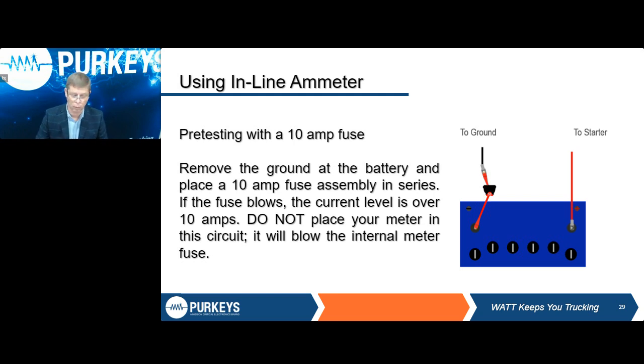What you want to do is, we always recommend doing the ground side. It's just safer, less likely to have sparks. So you're going to have to round up all your grounds that are connected to those batteries and bolt them together so you have one common junction point. Put that fuse holder in line. If it doesn't blow, it says, hey, you're under 10 amps, you should be fine to put your meter in. If it does blow, now you've got to do some more investigative checking to see what is my big load that's staying on.